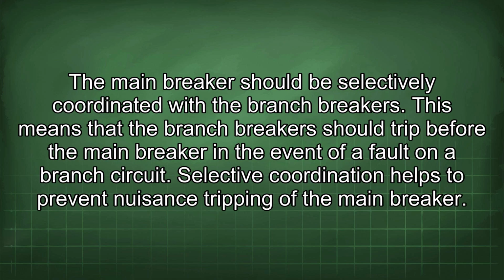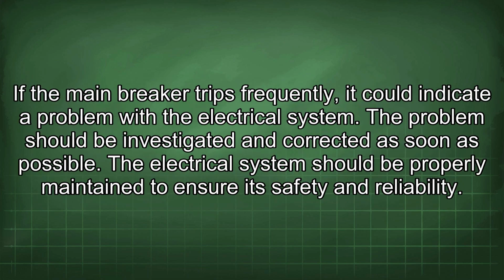The main breaker should be selectively coordinated with the branch breakers. This means that the branch breaker should trip before the main breaker in the event of a fault on a branch circuit. Selective coordination helps to prevent nuisance tripping of the main breaker. If the main breaker trips frequently, it could indicate a problem with the electrical system. The problem should be investigated and corrected as soon as possible.